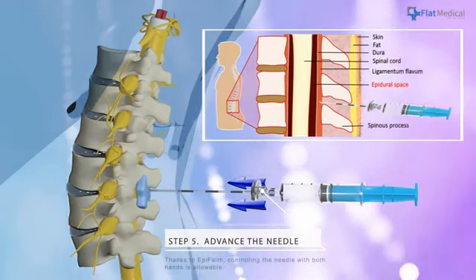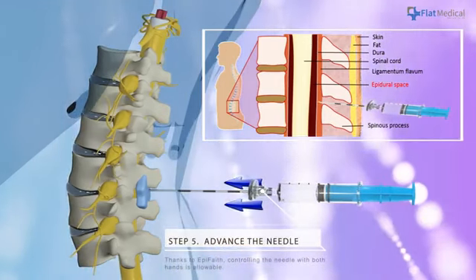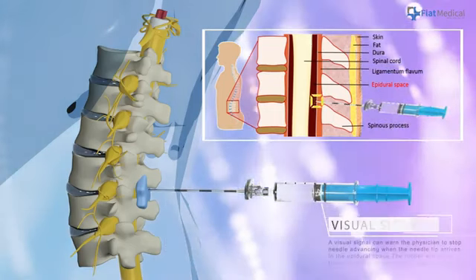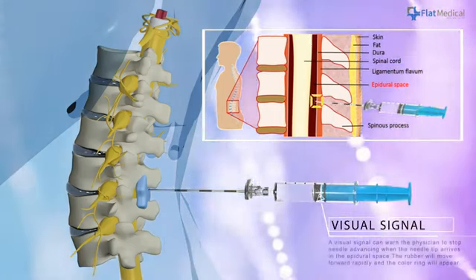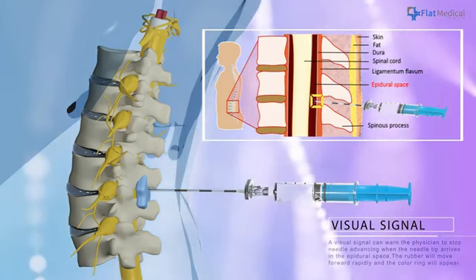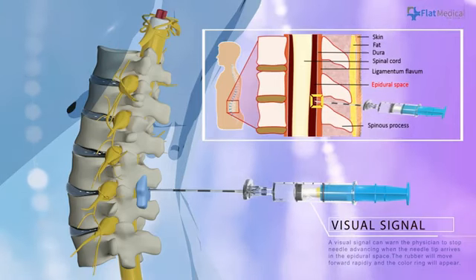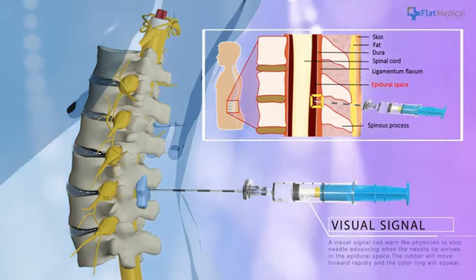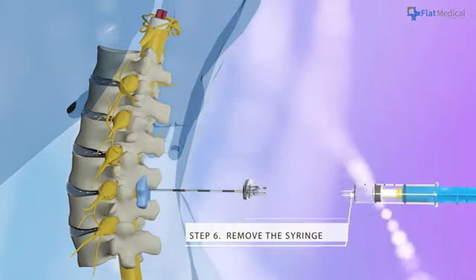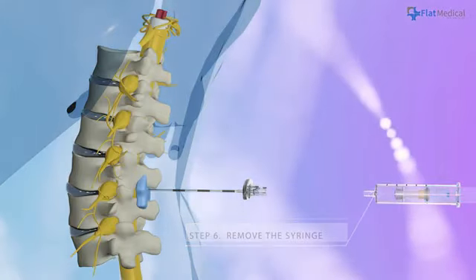Thanks to EpiFaith, controlling the needle with both hands is allowable. A clear signal can warn the physician to stop needle advancing. When the needle tip arrives in the epidural space, the rubber will move forward rapidly and the color ring will appear. Remove the syringe and insert the catheter to complete the injection.